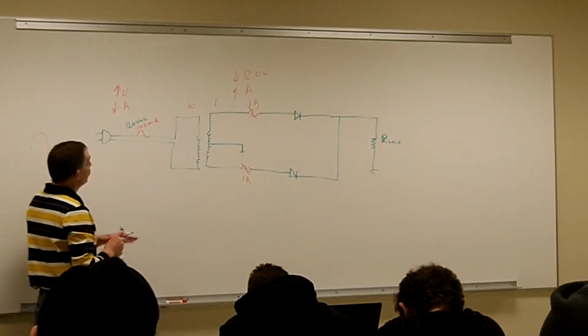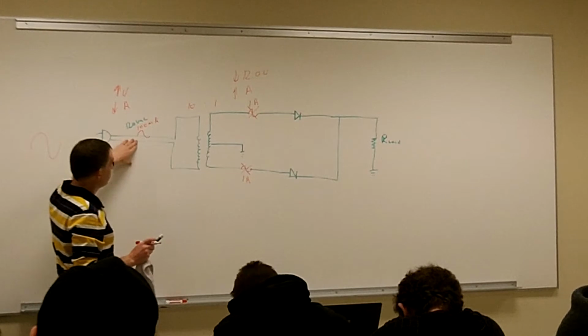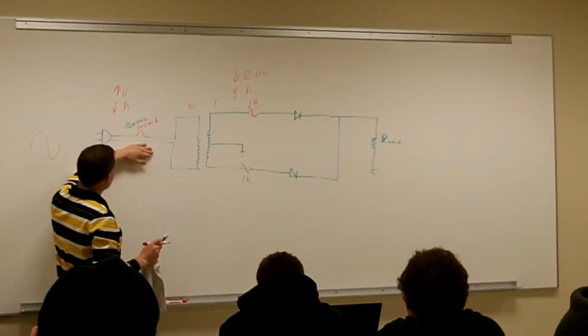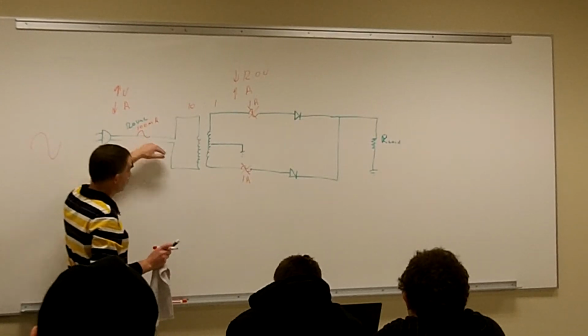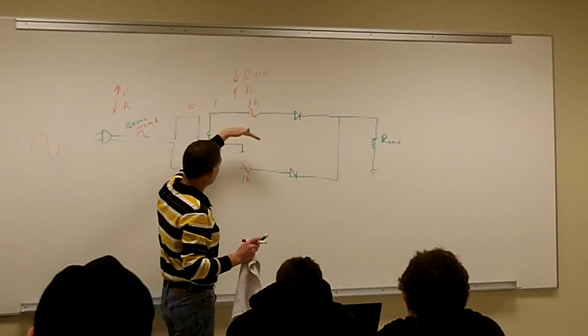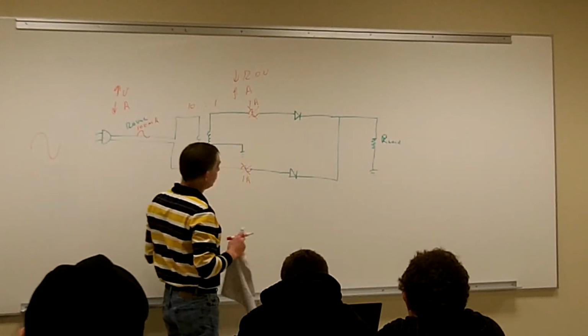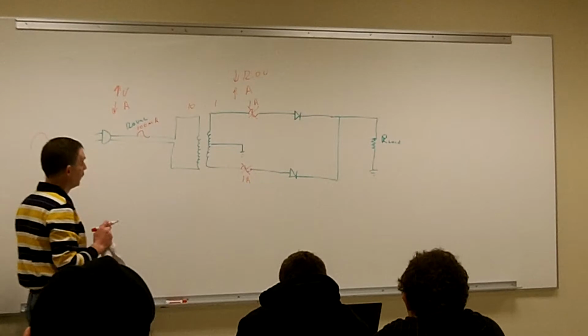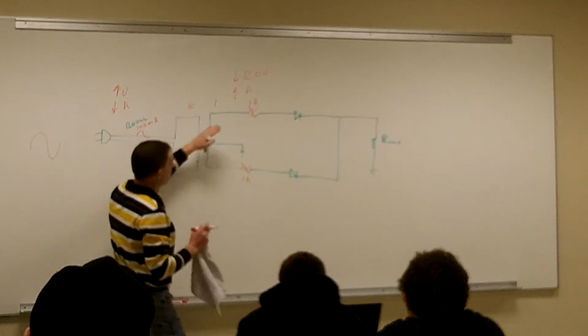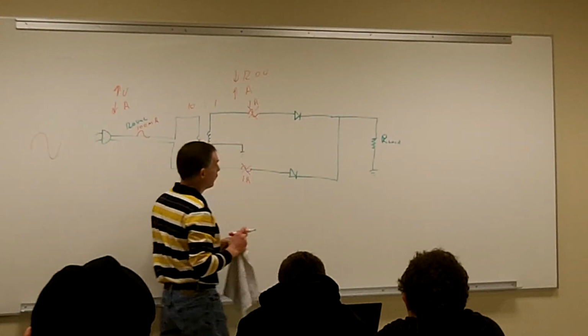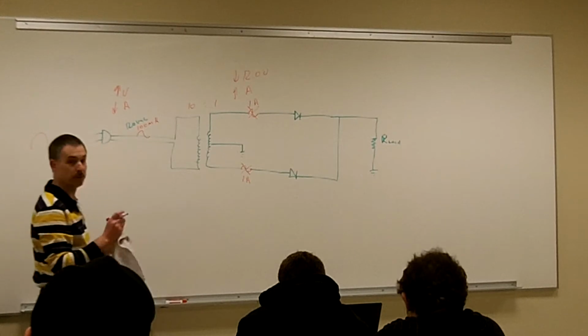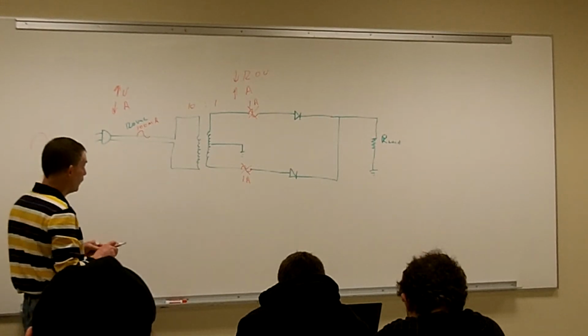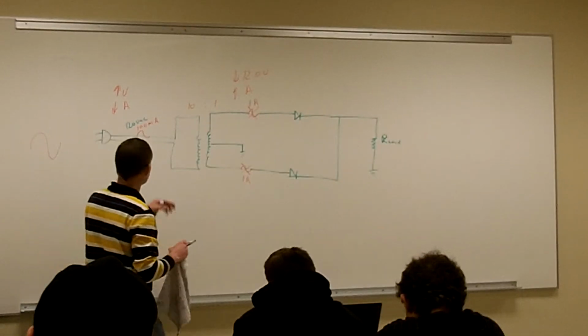Typically we always protect our primary side. This eliminates us having to put in two different fuses onto our secondary, because we can have multiple taps, some circuits up to 15 or 20 taps depending on what you're doing.